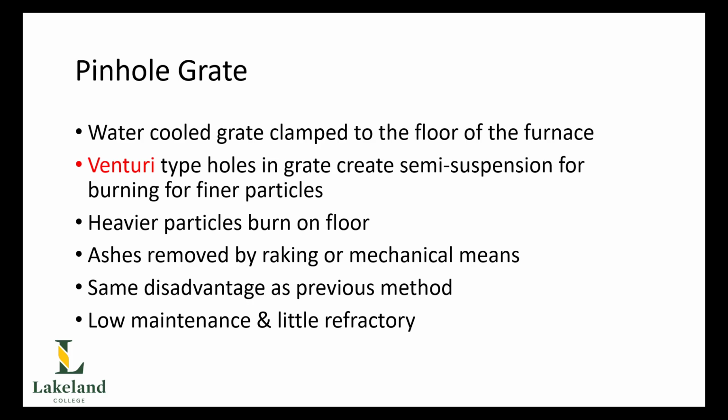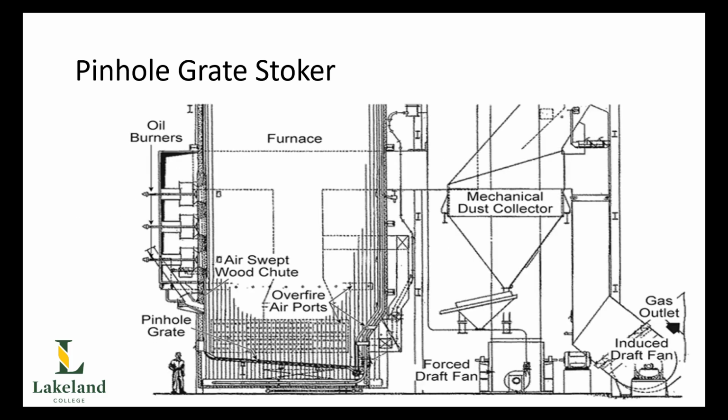Unfortunately, the ash in this type of furnace has to be removed in the same way as the Dutch oven. That is, by opening the side doors at intermittent times along the bottom of the furnace, inserting the rakes, and then manually raking it out. Again, a bit of a nightmare job there. Low maintenance and little refractory is required in a pinhole grate furnace, and of course that is why they're popular. The water-cooled grate is just going to increase our heat transfer surface area, thereby increasing the efficiency of our steam generator. So here's an example of a pinhole grate stoker.